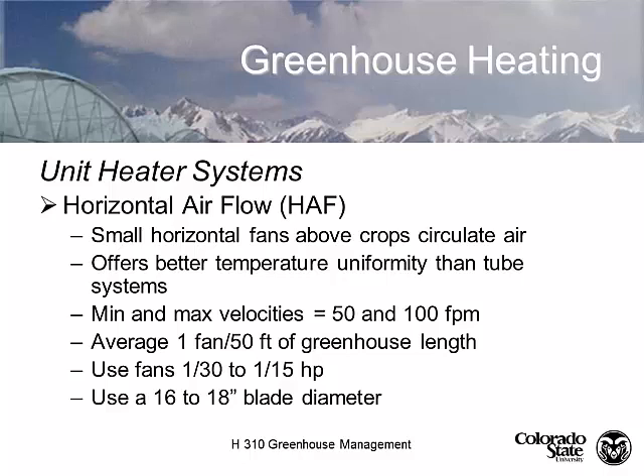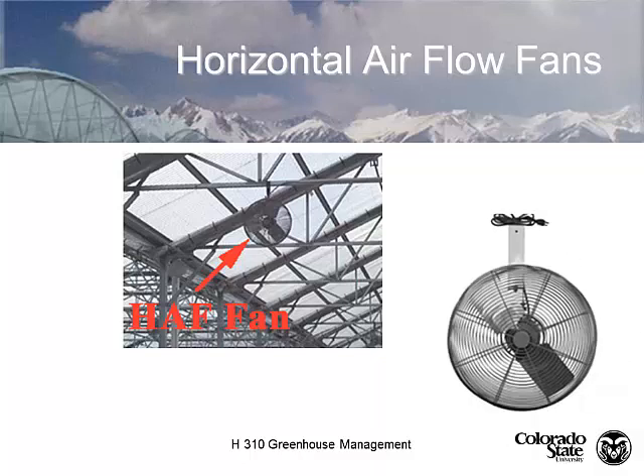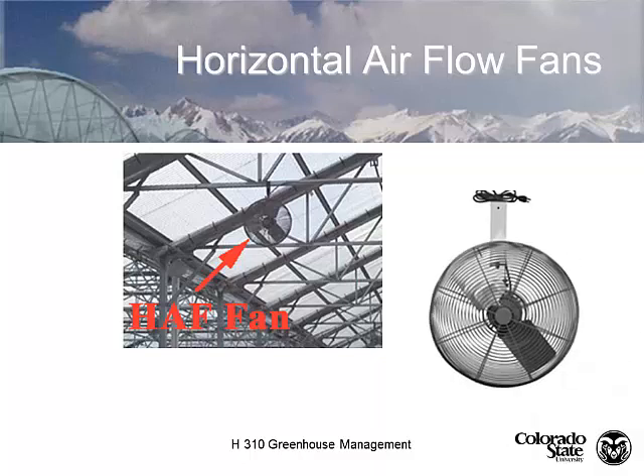HAF fans move air at about 50 to 100 feet per minute, using 1/30th to 1/15th horsepower. They're only about 16 to 18 inches in diameter — not a big fan — but they provide really uniform control of the greenhouse environment. Here's an HAF fan hanging about 10 inches below the truss. Most fans we see today are something like that.